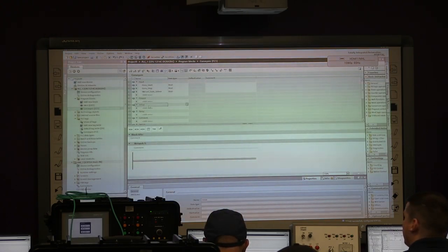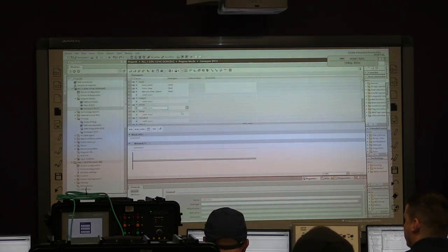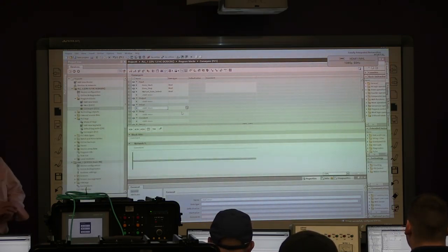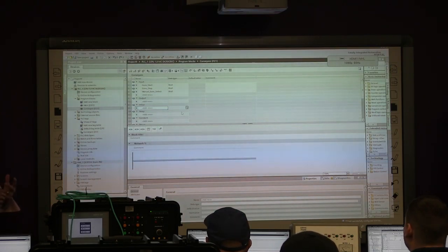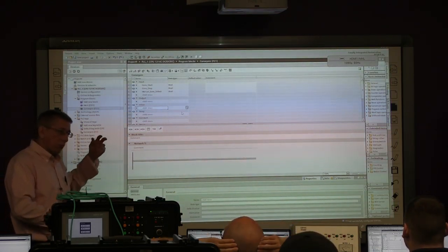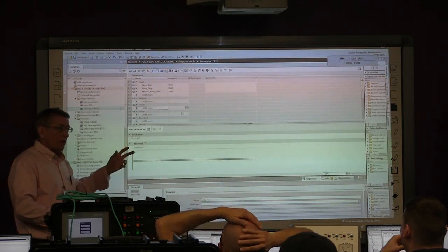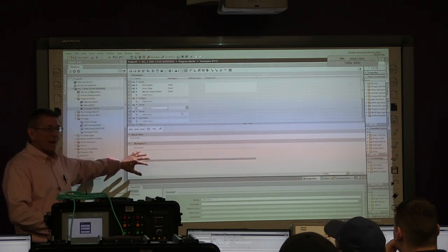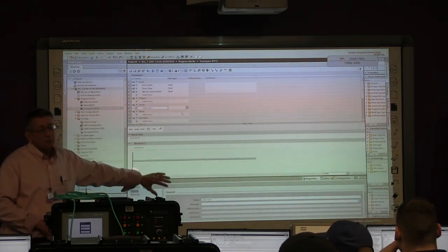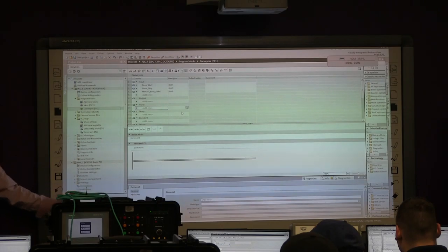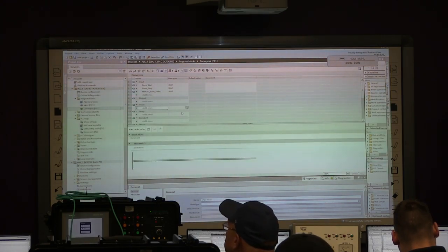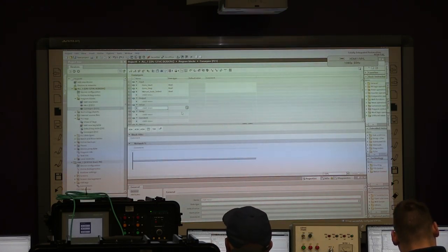Can we simply transfer these over? Are these just local tags? That's right, they're going to be all local tags. And here are a couple of rules when you're creating functions and function blocks, as we're doing, that's going to run multiple things like this. They'll contain all local tags. Siemens calls them variables. And technically, we don't have an output tag, and I'll show you why in just a second.